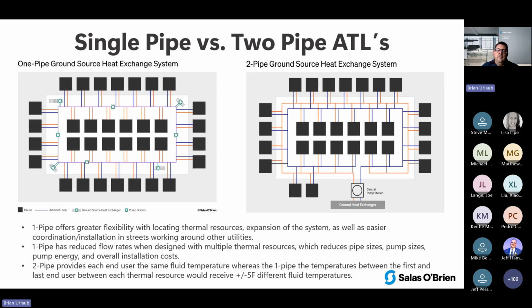So to have the extra pumping energy and all the additional piping costs, putting pipes in the street, one pipe versus two pipe, all that coordination and space, it's a lot. For me, in the thermal energy network space, the single pipe is really the driver to start with. And if it doesn't make sense, you can move to a two pipe. But at least from our perspective, we always start there as the first design approach.